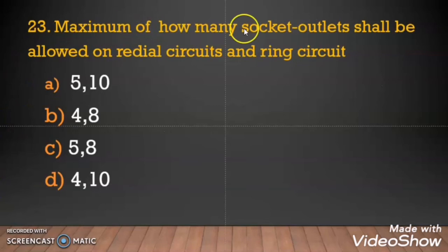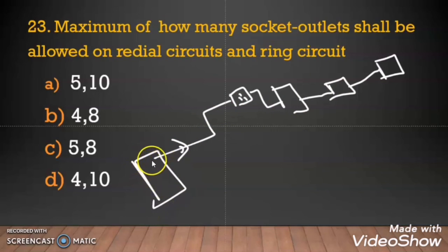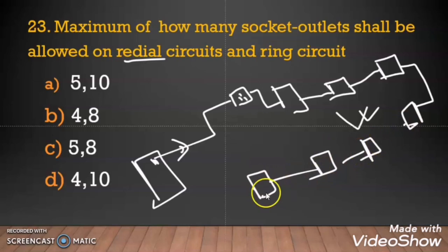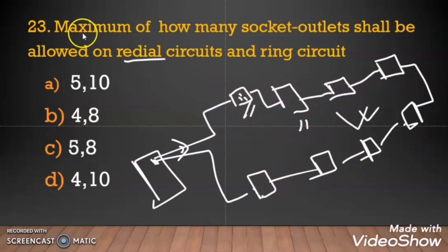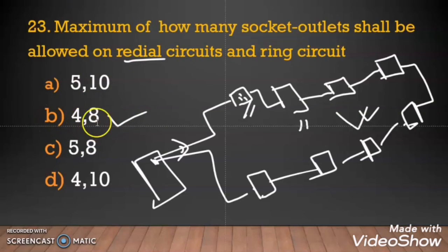Question 23: Maximum number of socket outlets allowed — for the radial circuit, maximum 4 is allowed, and for the ring circuit, maximum 8 is allowed. In a ring circuit, the outlets are looped and return back to the same circuit breaker. For DEWA regulation, 5 single sockets are allowed in radial and 10 in the ring. But as per ADDC regulation, the correct answer is option B: 4 for radial and 8 for ring.